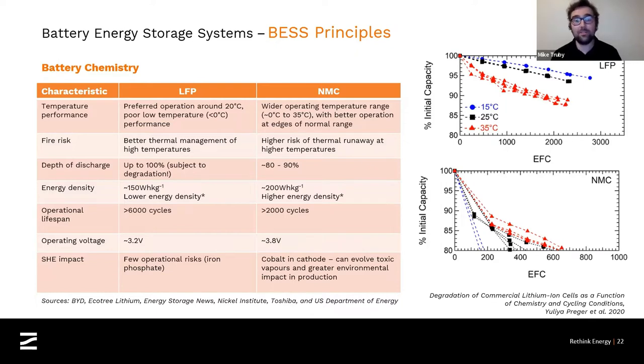The other part of that is that for static applications in practice, the energy density actually starts to balance out, because whilst you get more energy per cell in an NMC battery, you can actually pack LFP batteries much closer together. So when you're putting them onto an energy storage site, you could fit more batteries inside your building, inside your container, and it's easier to manage the temperatures that they generate. The other thing that is really beneficial about LFP batteries for static applications, for grid applications, is their operational lifespan.